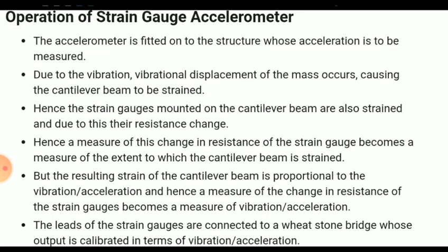The natural frequencies of systems using strain gauges are comparable to those systems which use LVDTs. Therefore, low natural frequencies are obtained with these systems. This is on account of the fact that large lengths of cantilever beams are used in order to accommodate the strain gauges. The primary advantage of the strain gauge accelerometers over the piezoelectric type is that they are more sensitive.